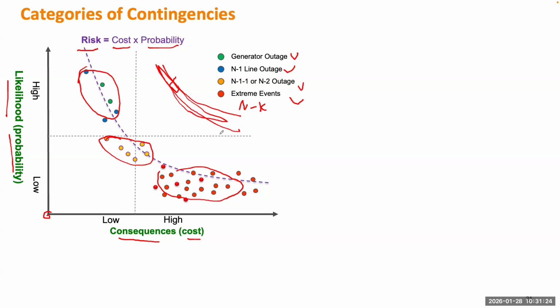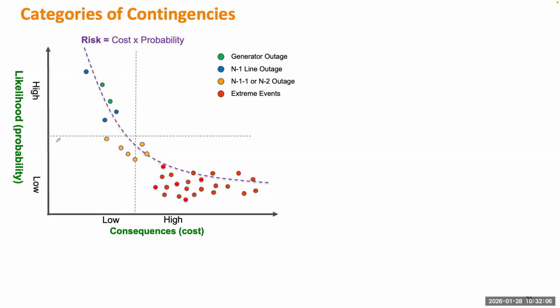Or we can just say, if we partition the entire plane into 4 regions, this region is the high cost, high likelihood region. This should never happen. As a planning engineer, you need to make sure that any contingency which can cause problems will stay close enough to the X or Y axis. But how about this corner? This corner means the cost is very low and the probability is also very low. So why do we need to study it? Right? It's not even worth studying this one. We just ignore this one. So finally, pretty much all the contingencies the planning engineer needs to study will be around those 2 regions, or finally, they will stay along this curve, with roughly about the same risk.